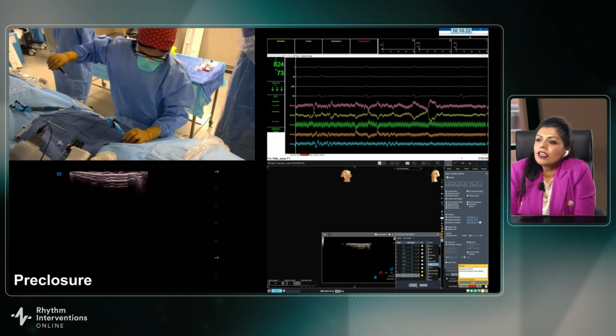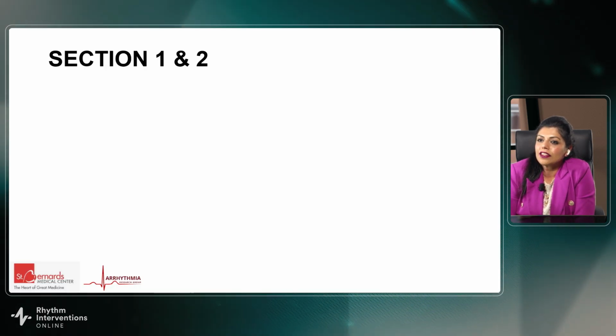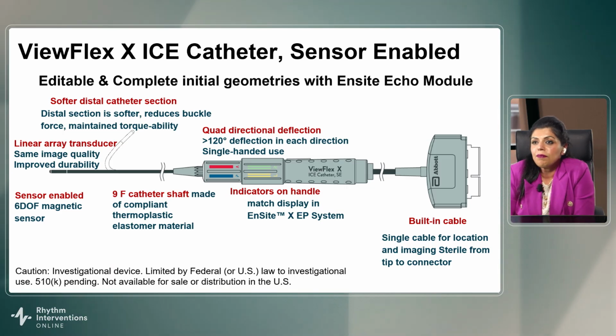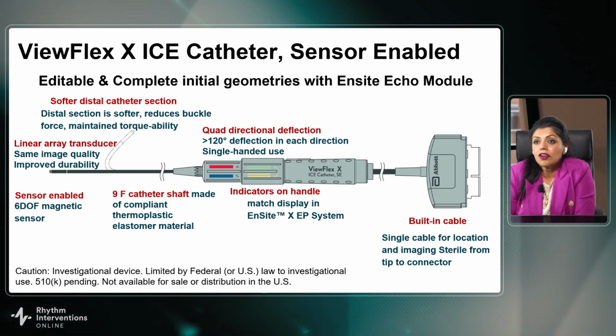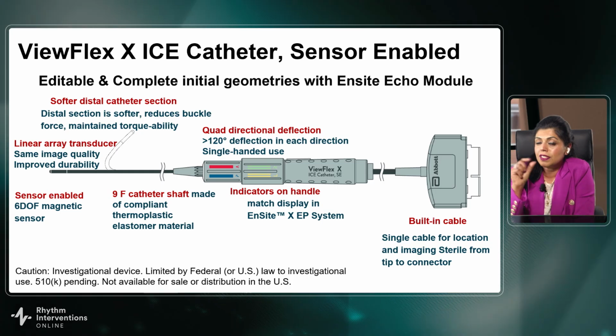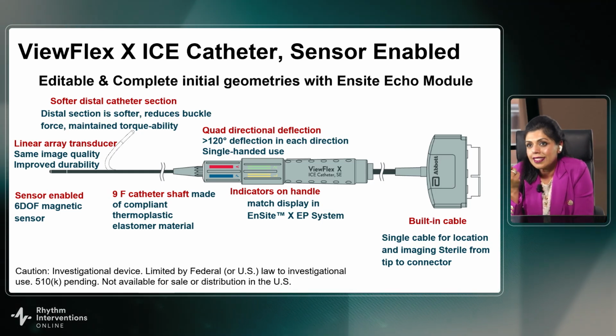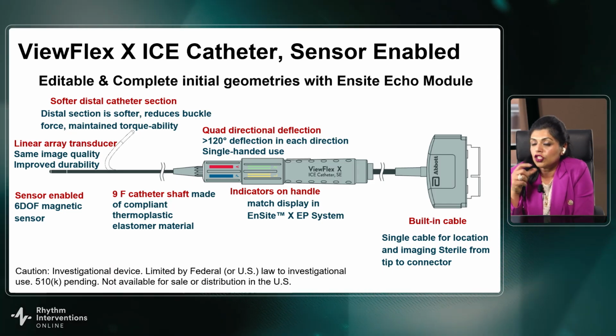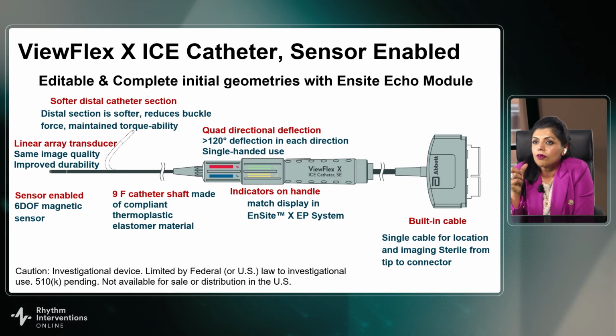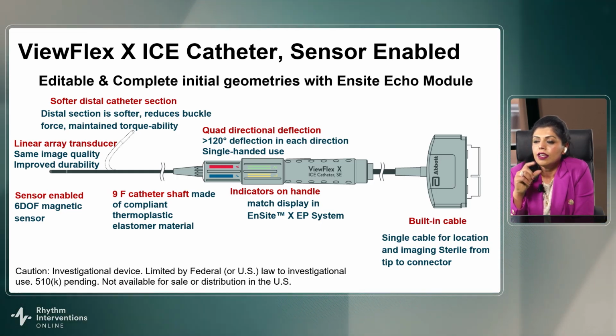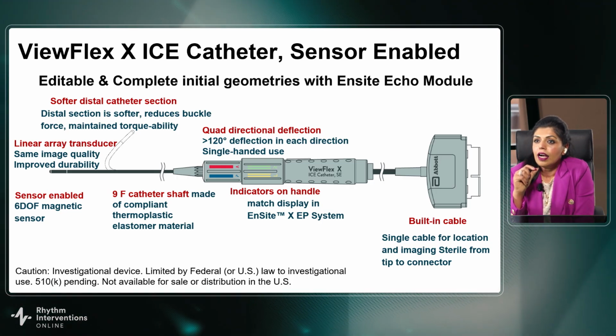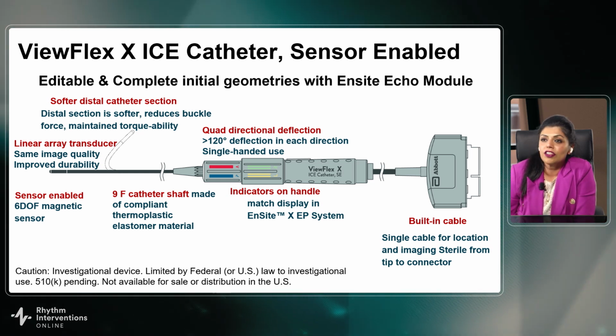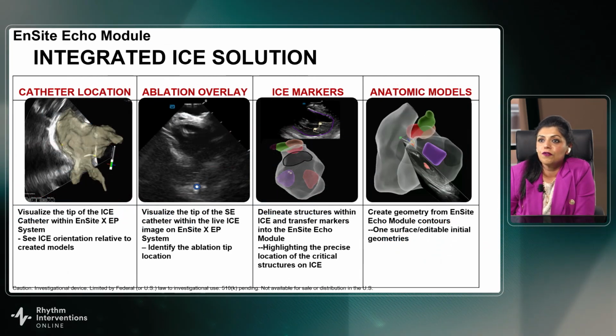So we'll be showing the ViewFlex ICE catheter. The ViewFlex ICE catheter is the new ICE catheter that will be integrated with the Abbott mapping system, the NavX system. It has a little sensor at the end that's going to show up on the NavX system. It's still the same 9 French catheter. It has the quad directional deflection that we're used to, and also the same linear array transducer that has the same image quality that we're used to with the ViewFlex system. Of course, it still has the built-in cable and all the other features that come with the ViewFlex ICE system.